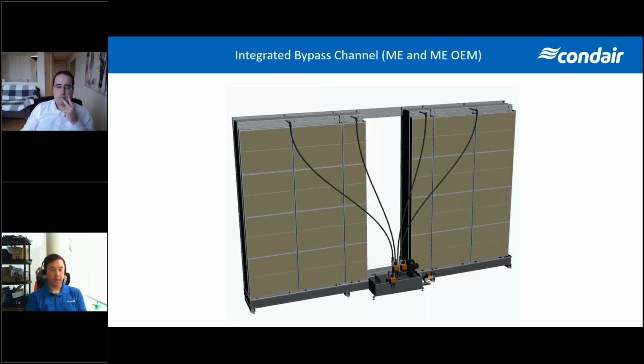So that's effectively what we've done here: designed a single system with 1 pump, 1 set of controls, 1 sump, but 2 banks of media with a 24-inch section left in the middle where the client could integrate their own bypass damper for additional humidification or cooling control.